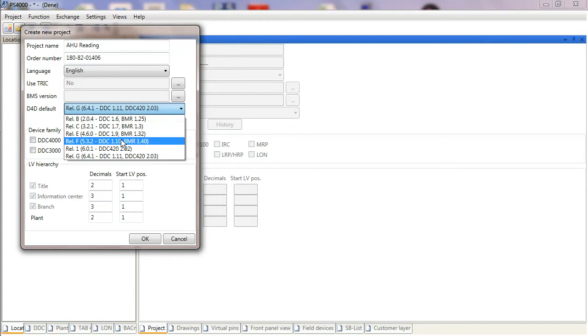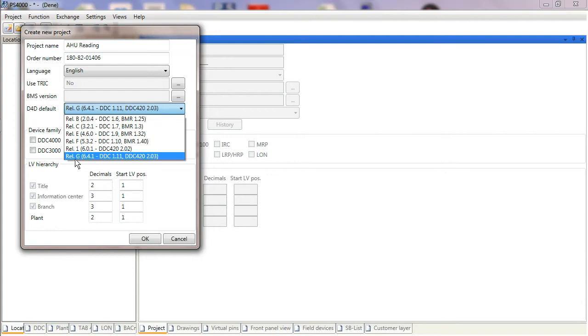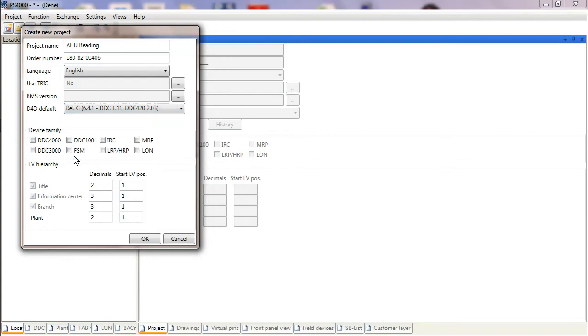It's always best to try and keep them all the same firmware version. If the site is working fine, there's no need to update. We'll keep it as release G, and then the final setting we need to make is DDC 4000 for our device family. I must make sure I tick DDC 4000 before I progress, which I'm now ready to do.